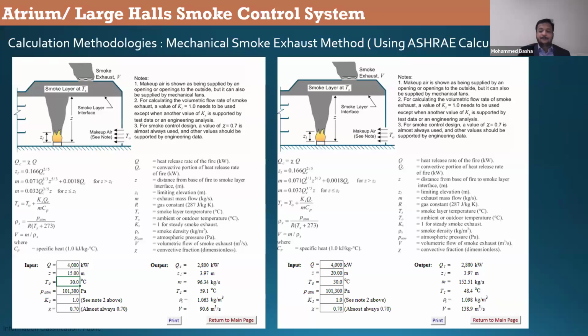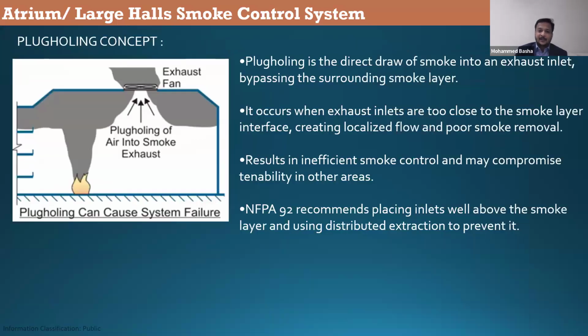Okay, now guys, with this figure, what you can understand is, if I provide a smoke extract of this volume, 138.9 meter cube per second or 90.6, with a smoke extract fan, one number at the top with an outlet, it will be working, right? Yes, it should work, but this is not how the code is telling, or how the smoke behaves. If you keep only one smoke exhaust fan or one smoke exhaust outlet, you will end up failing the system. There is a concept called plug holing. This is called plug holing.